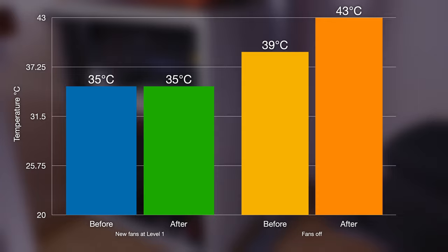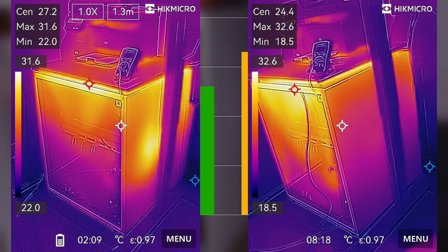You can also see it on the thermal image. If I pull up the thermal image I showed before, and then also pull up a new thermal image I took after putting the sound insulation in, you can clearly see that the sides of the rack with the sound insulation don't have nearly as much heat leaking out of them. So it's definitely very important to have the cooling system.